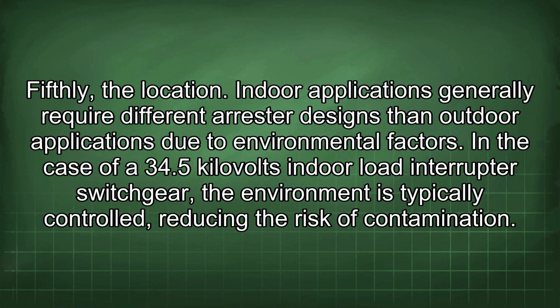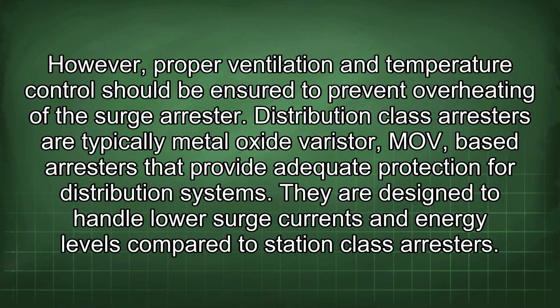Fifthly, the location. Indoor applications generally require different arrestor designs than outdoor applications due to environmental factors. In the case of a 34.5 kV indoor load interrupter switchgear, the environment is typically controlled, reducing the risk of contamination. However, proper ventilation and temperature control should be ensured to prevent overheating of the surge arrestor.